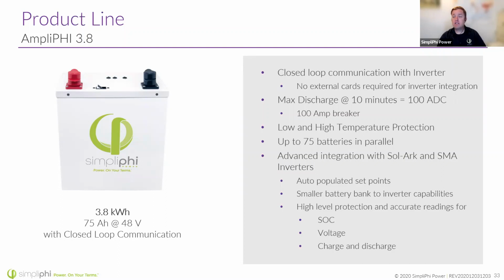It has a max discharge of 100 amps at 10 minutes. Just to go back, the PHI 3.8 has 80 amps at 10 minutes, so this one has a slightly higher max discharge. So if you've got well pumps, a lot of motors to start, it might be a situation where you want to look at the AmpliPHI. It's the same size, so it's going to fit into the same wall brackets and battery cabinets as the standard PHI does. This one has built-in temperature protection.